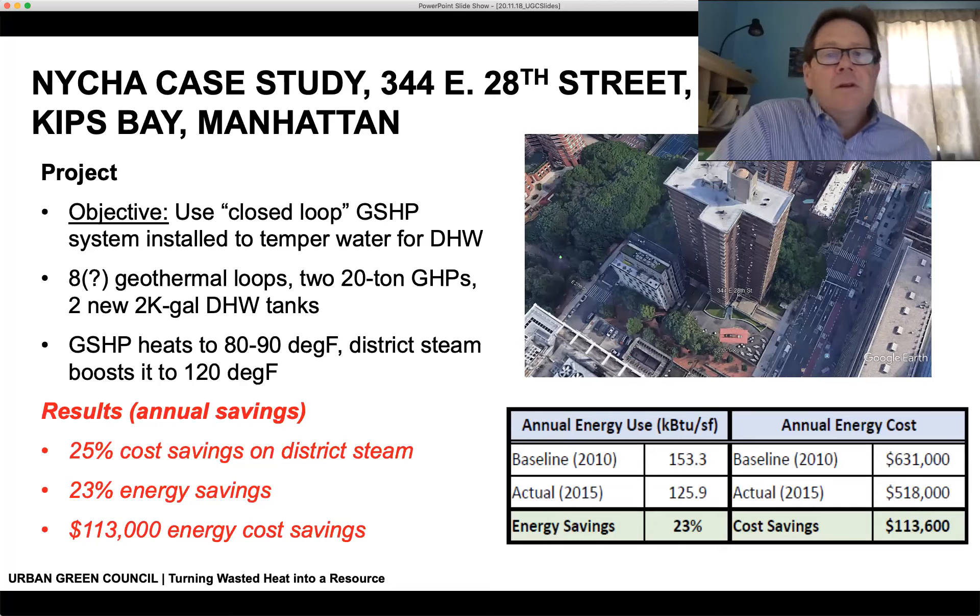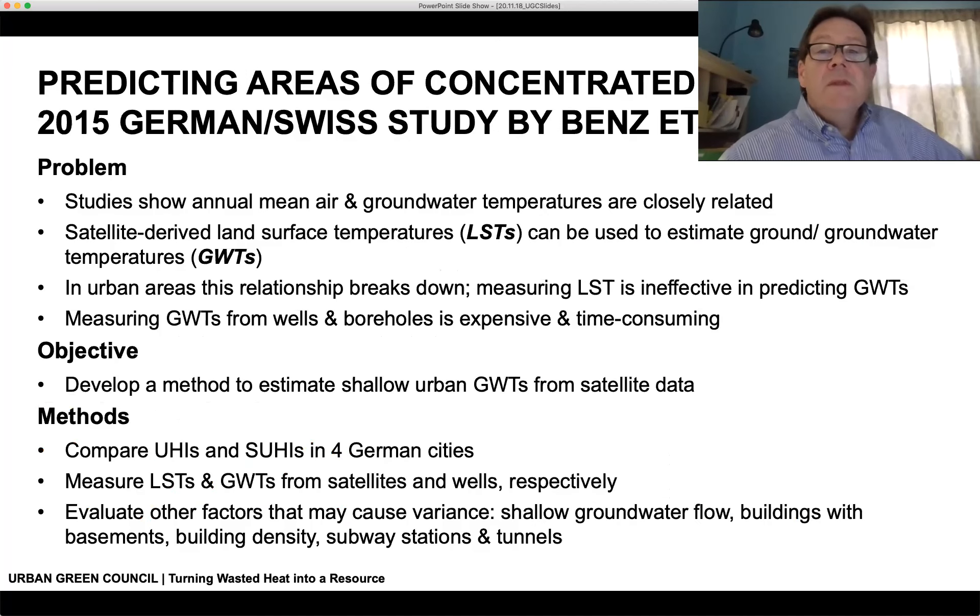In 2012, NYCHA implemented a $2.2 million lighting, heating, and hot water modernization project, partially funded by ARRA funds and NYCHA's capital fund. They installed a geothermal closed-loop system — approximately eight geothermal loops installed in the courtyard area — connected to two 20-ton geothermal heat pumps, with new domestic hot water tanks. The intent was to use the ground to temper the water, bringing it up to 80–90°F, with district steam taking it the rest of the way. Results: 23% energy savings and 25% cost savings on the district steam used for domestic hot water.